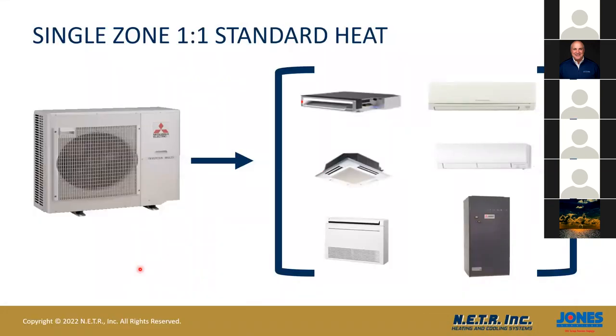So let's look at what can come in. When we talked about the one-to-one standard heating zones, because we have different types of heat pumps. We have what's called the standard heat pump that will heat down to roughly around 17 degrees to 20 degrees at a full source of heat. Anything below that, we're not going to get the capacity out of it. We would need to move to a different model. But these can be run one-to-one, one outdoor unit, one indoor unit.